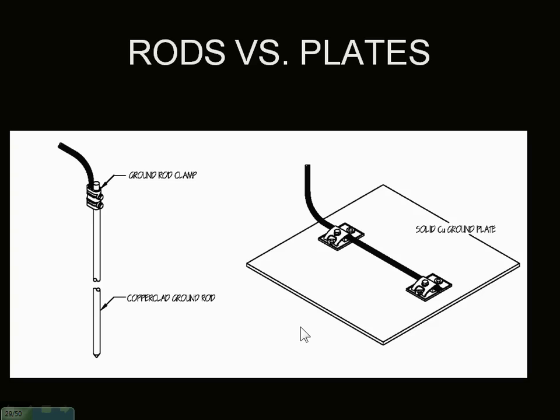But here's what you can tell them. Tell them in the lightning industry, there's no circuit breaker that's going to trip when you hit lightning. The reason why we have this 5 ohms and 25 ohms is if you have a ground fault, and it's high impedance to the ground, your circuit breaker is not going to trip fast enough. But you guys don't have a circuit breaker to trip. We don't, which is why there's no requirement. So okay, that's good to know. It has to do with the tripping of the circuit breakers and the blowing of the fuse. And we don't have to worry about that because all of ours is basically a dead wire until it gets activated.